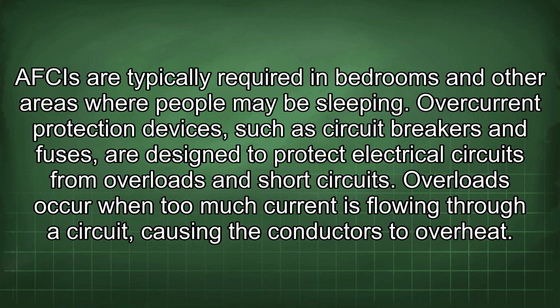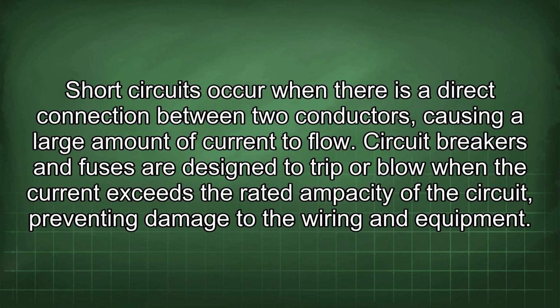Overcurrent protection devices, such as circuit breakers and fuses, are designed to protect electrical circuits from overloads and short circuits. Overloads occur when too much current is flowing through a circuit, causing the conductors to overheat. Short circuits occur when there is a direct connection between two conductors, causing a large amount of current to flow. Circuit breakers and fuses are designed to trip or blow when the current exceeds the rated ampacity of the circuit, preventing damage to the wiring and equipment.